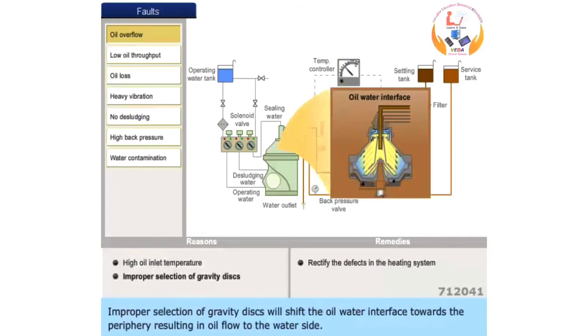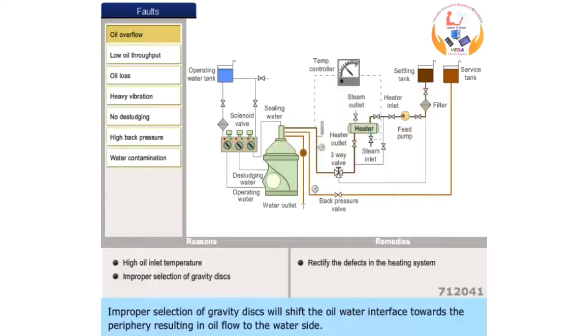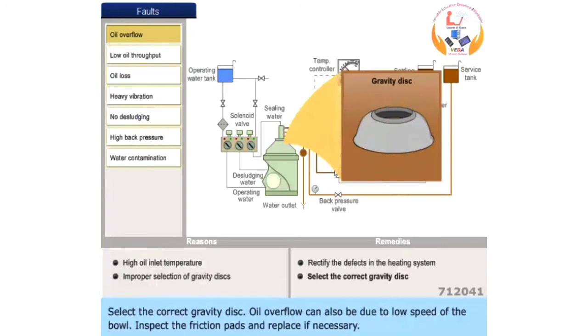Improper selection of gravity disks will shift the oil-water interface towards the periphery, resulting in oil flow to the water side. Select the correct gravity disk.